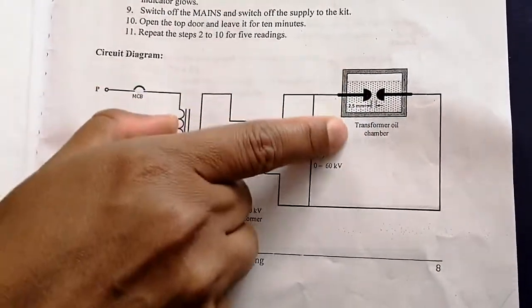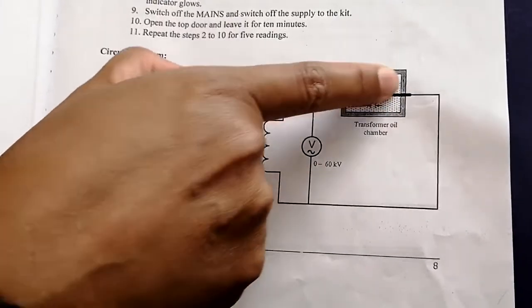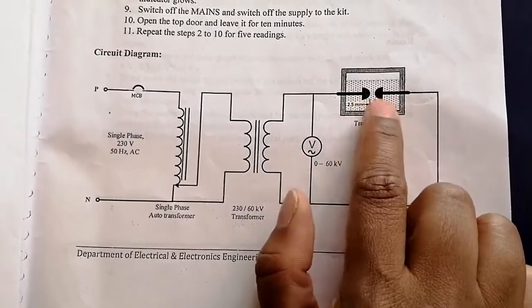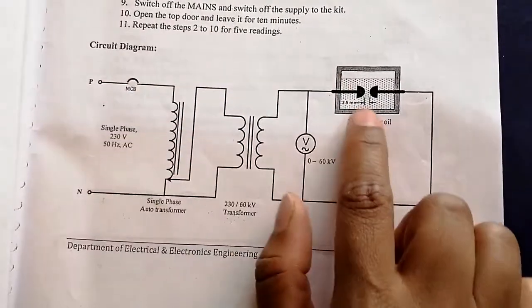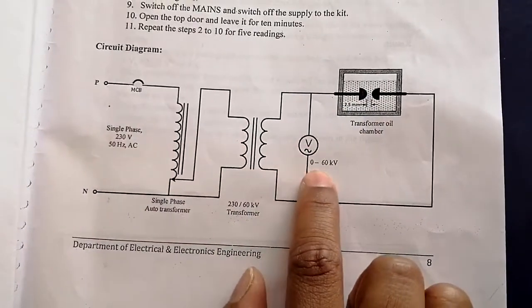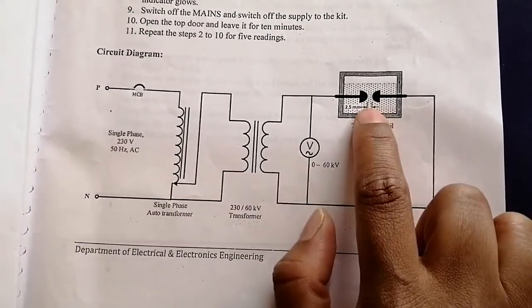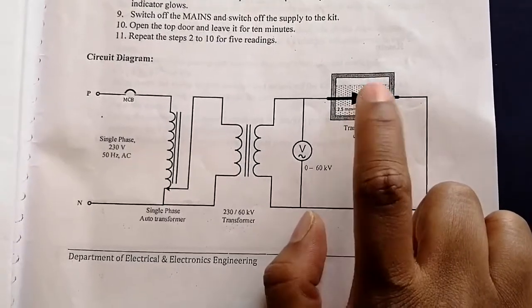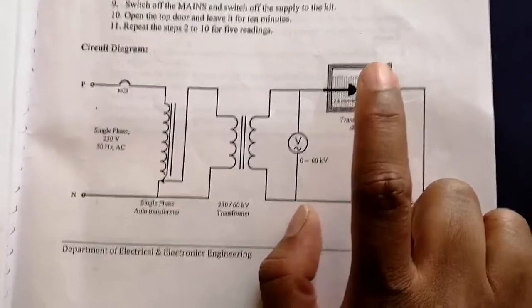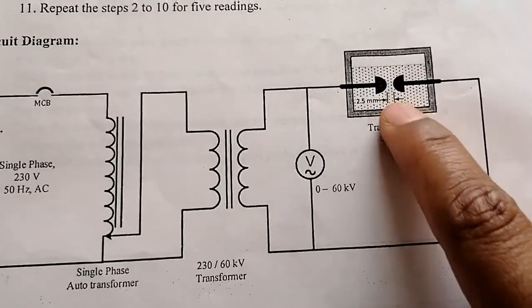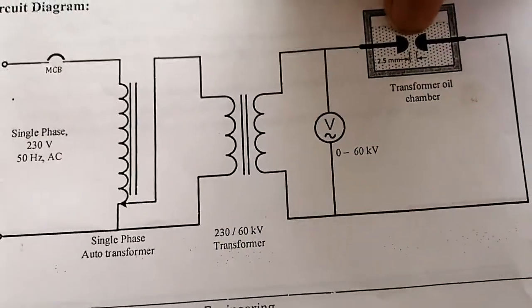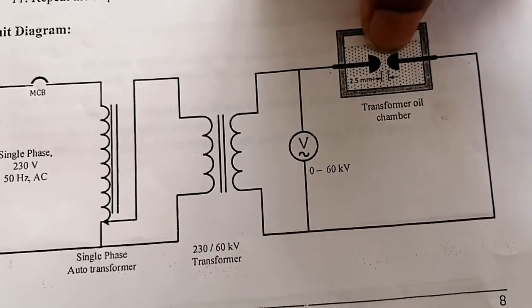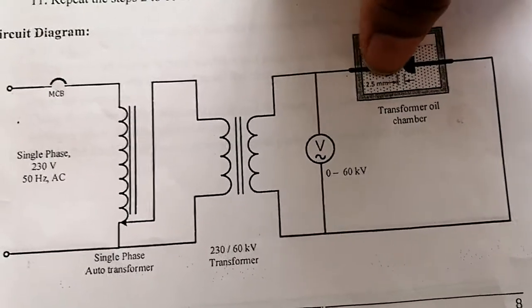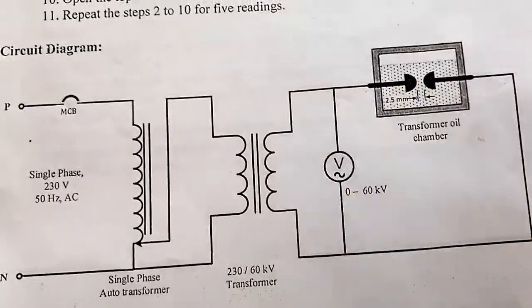And this is the transformer oil kit apparatus. It is a glass apparatus where you can fill the oil in the tank. This is a sphere gap, used to apply the high voltage. If I keep applying a voltage from 0 to 60 kilovolt, at a certain voltage value the oil will break down and you can see the spark. Now we have to set the distance between the two spheres. But in your lab experiment there is no need to set it, because we have already preset a 2.5 mm gap between the sphere rods, which you can see now.